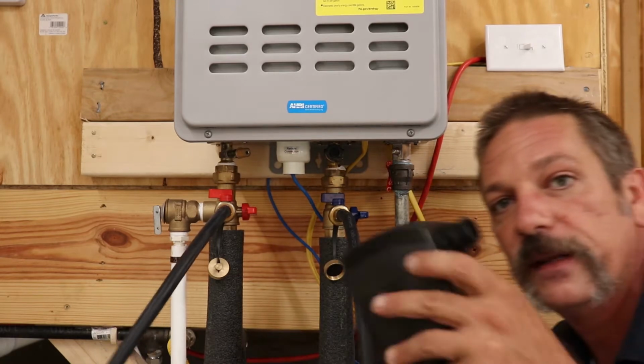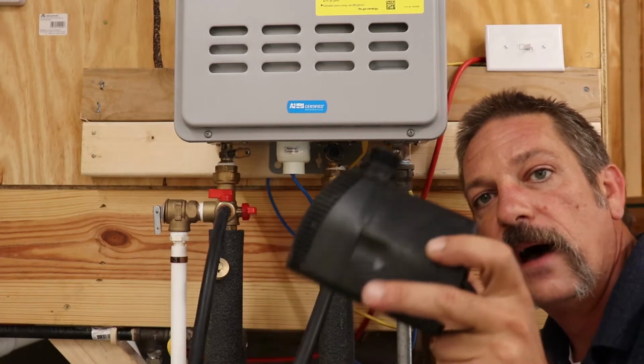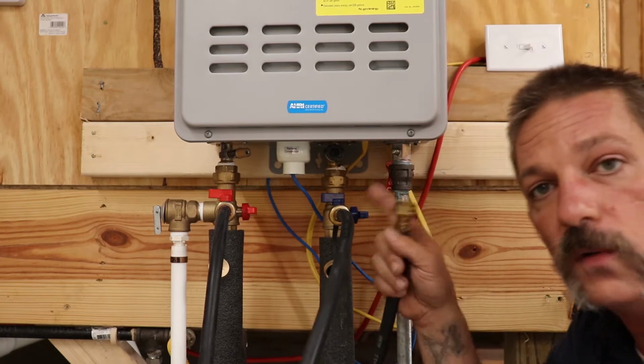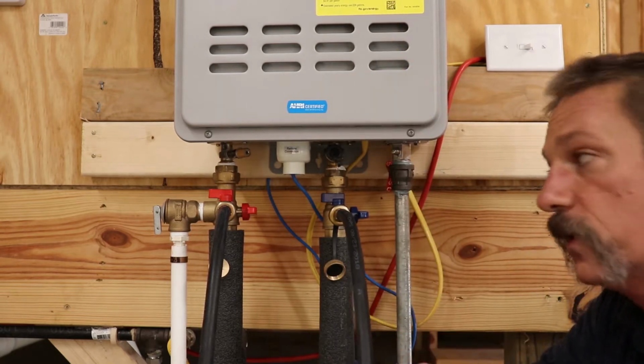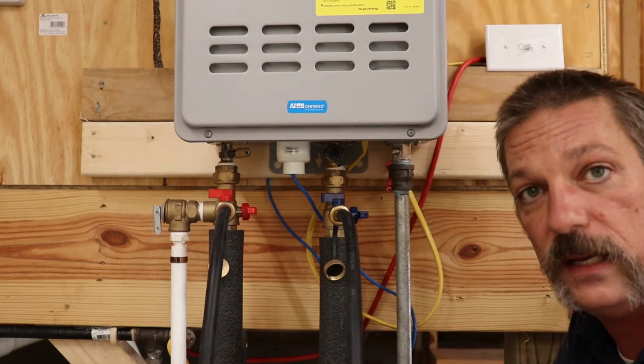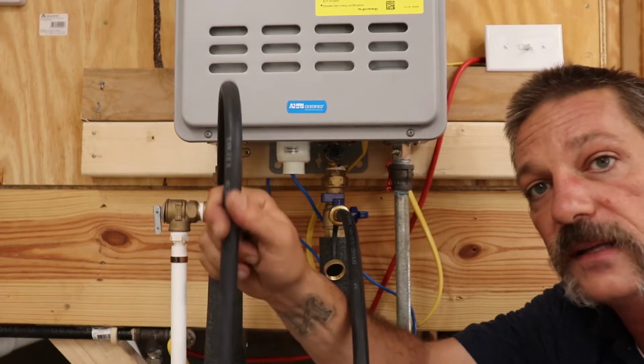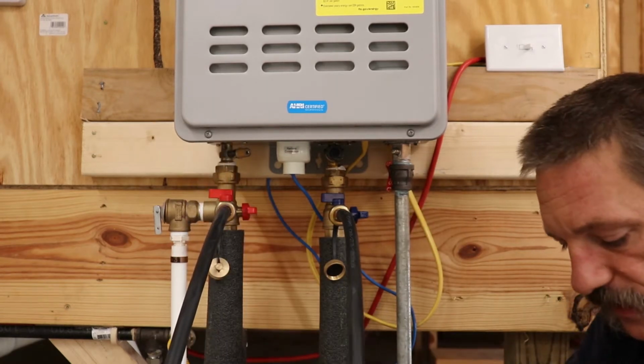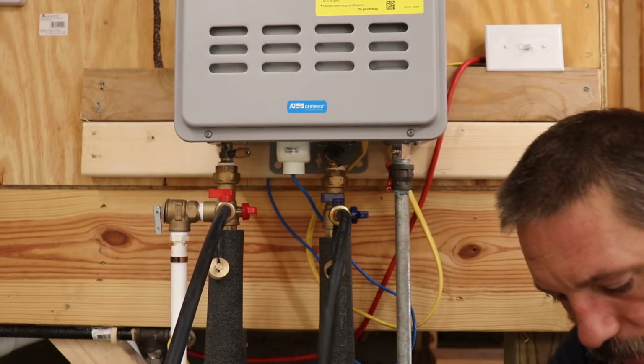And then you're going to have a little pump. Hook your cold side hose into the top of the pump. You're going to blow it through the cold side, up through that heat exchanger, and then return it back to your bucket with the hot side line.